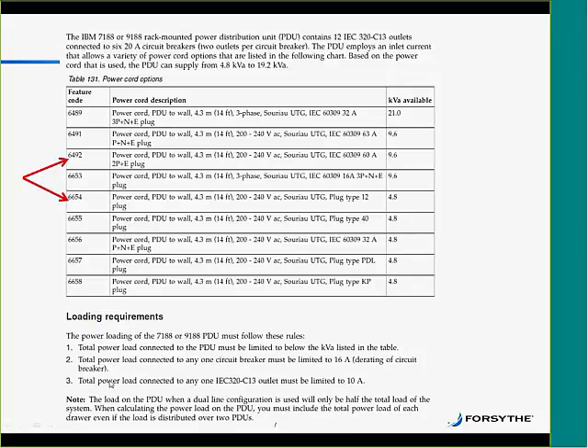And then, as I said here, the total power load connected to any C13 outlet must be limited to 10 amps. And that's one of the reasons why you'll see with the S824 and the E870, they now have 4 power plugs instead of 2, because the E870 pulls 19 amps. Well, you can't plug that into one 10 amp plug. So what you do with the E870 is you take those 2 plugs and you put them into 2 separate pairs on the same PDU, and now you're inside of the rules.